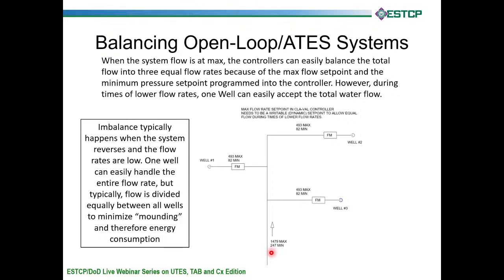In this scenario, let's pretend we're at minimum flow, which is just one of these cold wells pumping, and that pump is running at 50%. So now our system flow rate is 247 gallons a minute. Well, ideally, we'd want 82 to go here, and 82 to go here, and 82 to go here. But one well can easily accept 493 with no problem. So we know it can take 247.